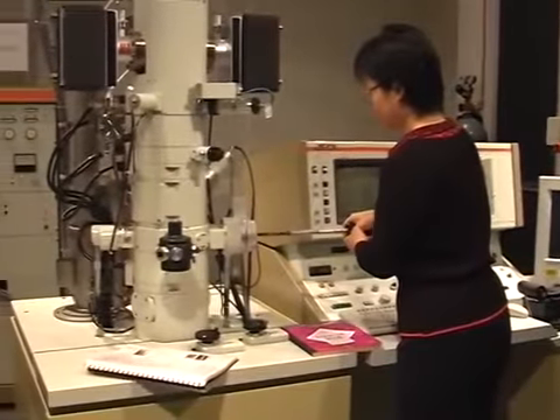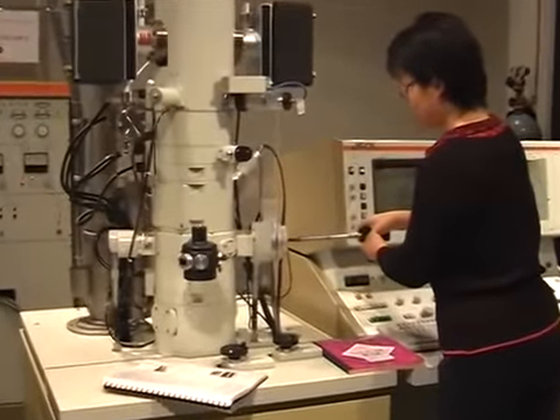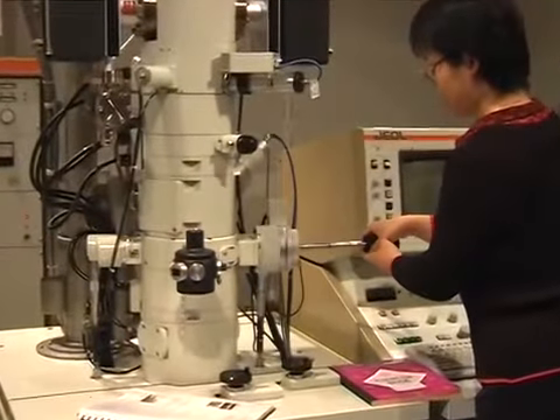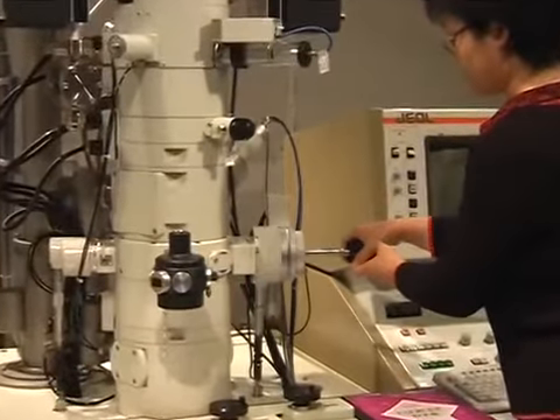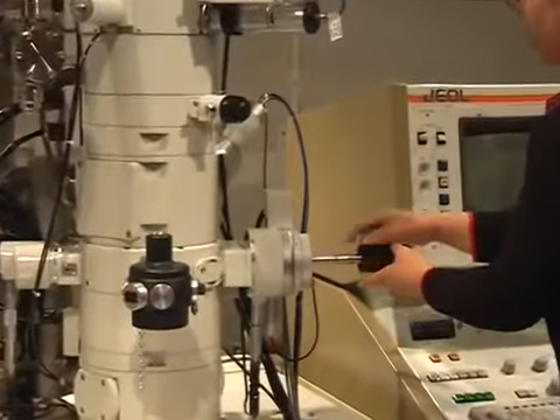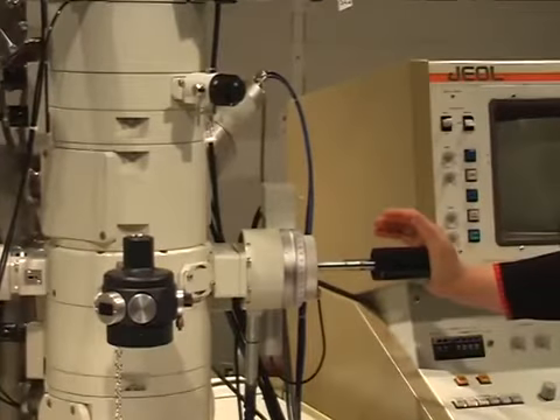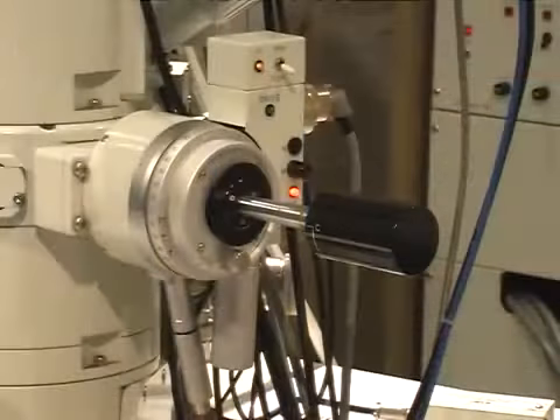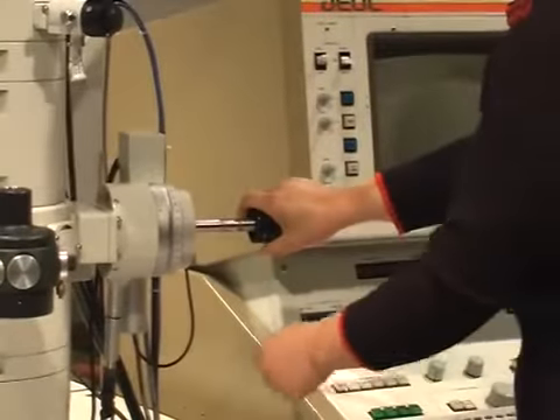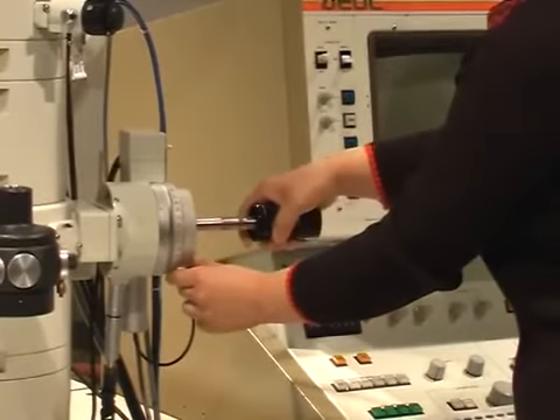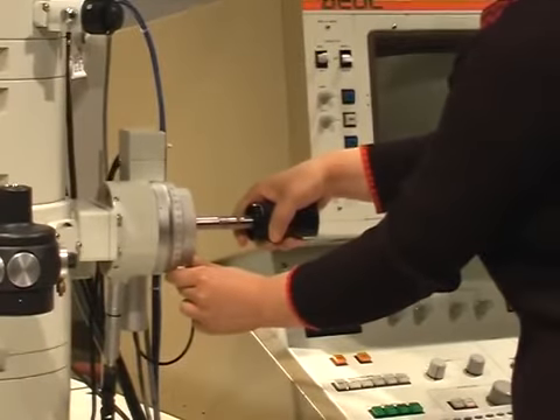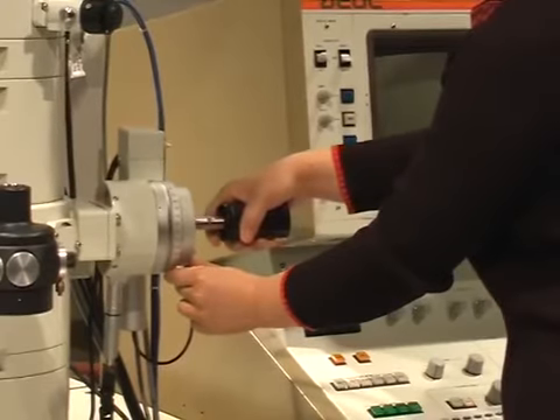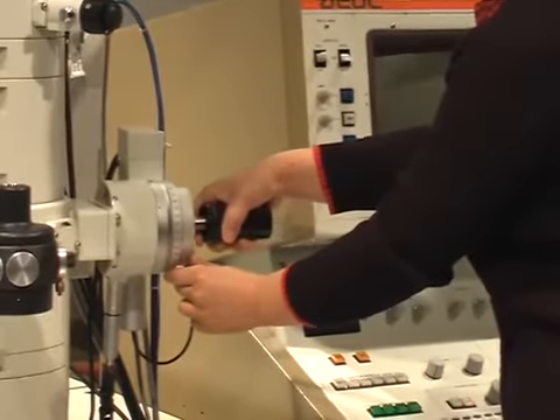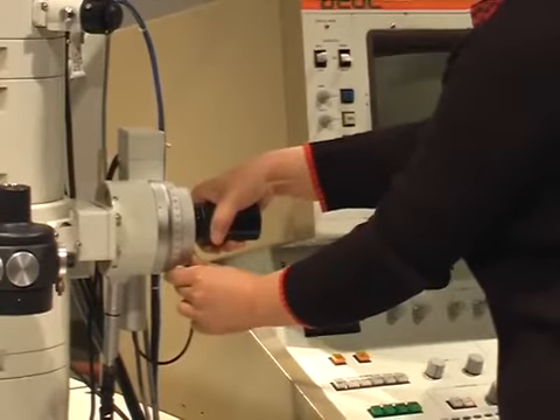Carefully slide the sample holder into the goniometer until the sample holder comes to a stop. The key should have just gone into the keyway and no longer be visible. Push the sample holder in about 2 millimeters. The red evac light will turn on. After about 30 seconds, the red evac light will go out. Slowly rotate the sample holder clockwise by 90 degrees until a stop is reached.